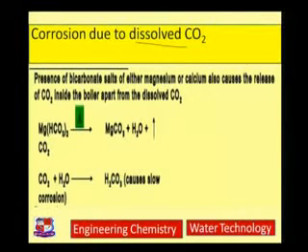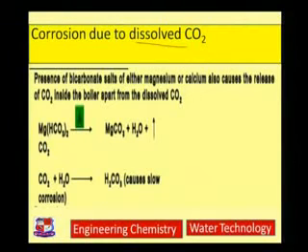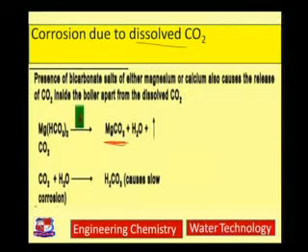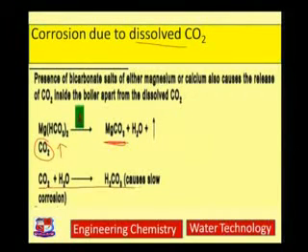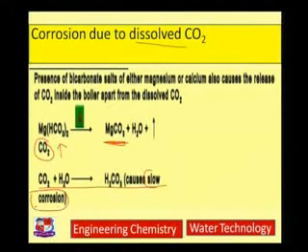Bicarbonate salts causing temporary hardness get converted to carbonates in the boiler upon heating, and carbon dioxide is released in this process. This carbon dioxide may form carbonic acid, and this carbonic acid may cause slow corrosion of the boiler material. So carbon dioxide obtained from hardness-causing salts causes boiler corrosion.